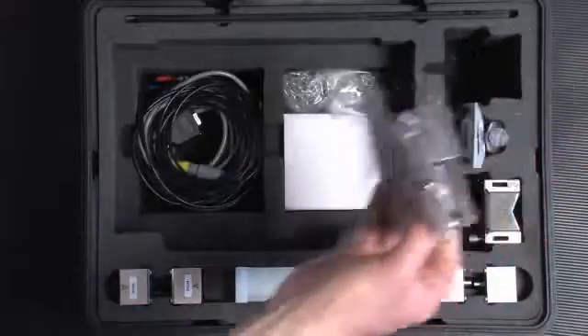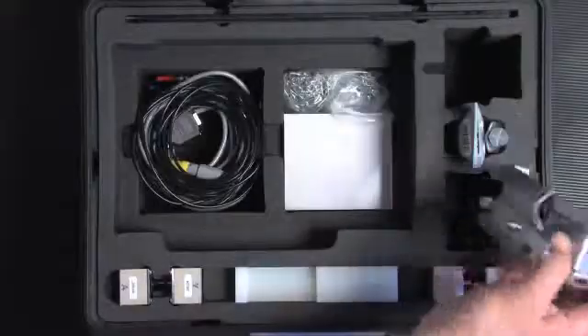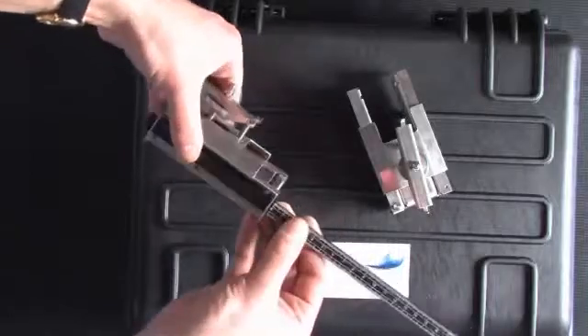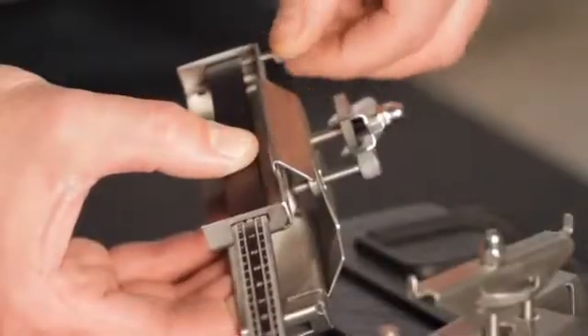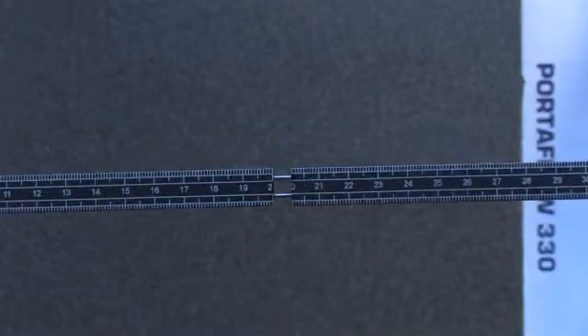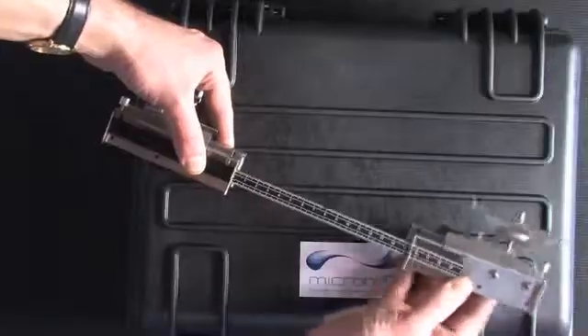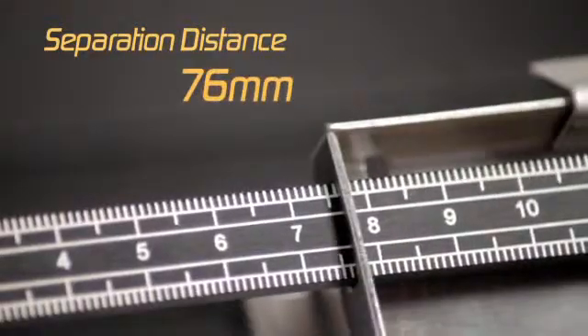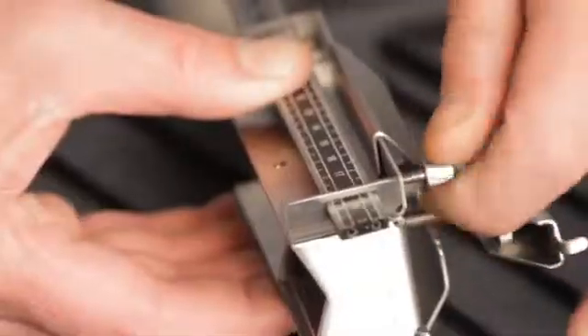Now we need to set up the guide rail and the ruler. Slide the ruler into the guide rail and position it at zero, tightening up the screws to ensure no movement. Depending on the pipe size and separation distance calculated, you may need to attach the ruler extension. Take the second guide rail and position this at the other end of the ruler at the separation distance calculated by the unit, tightening up the screws.